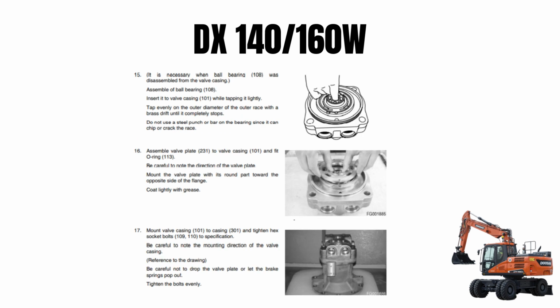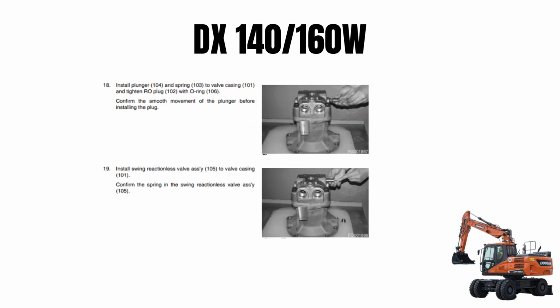A ball bearing was disassembled, so assemble the ball bearing again with the housing. Insert the valve casing and tap it lightly. Assemble the valve plate and fit the O-ring also. Mount the valve plate with its round part toward the opposite side of the flange. Mount the valve casing and tighten the hex socket bolts to specification.